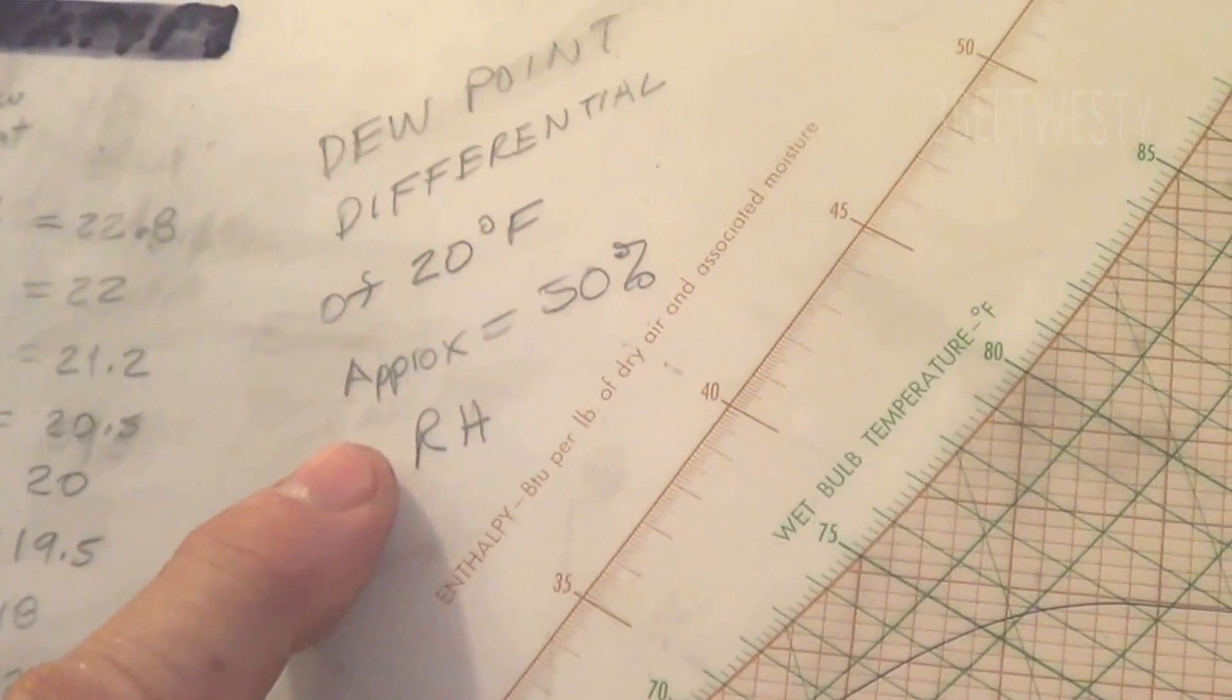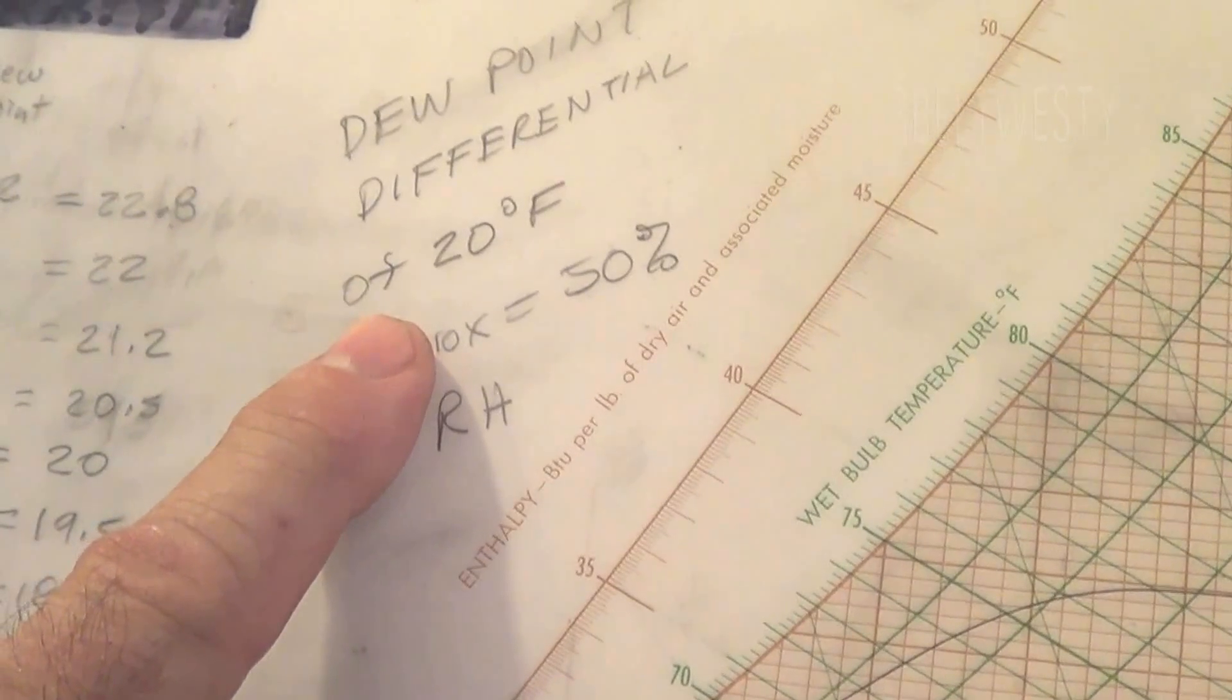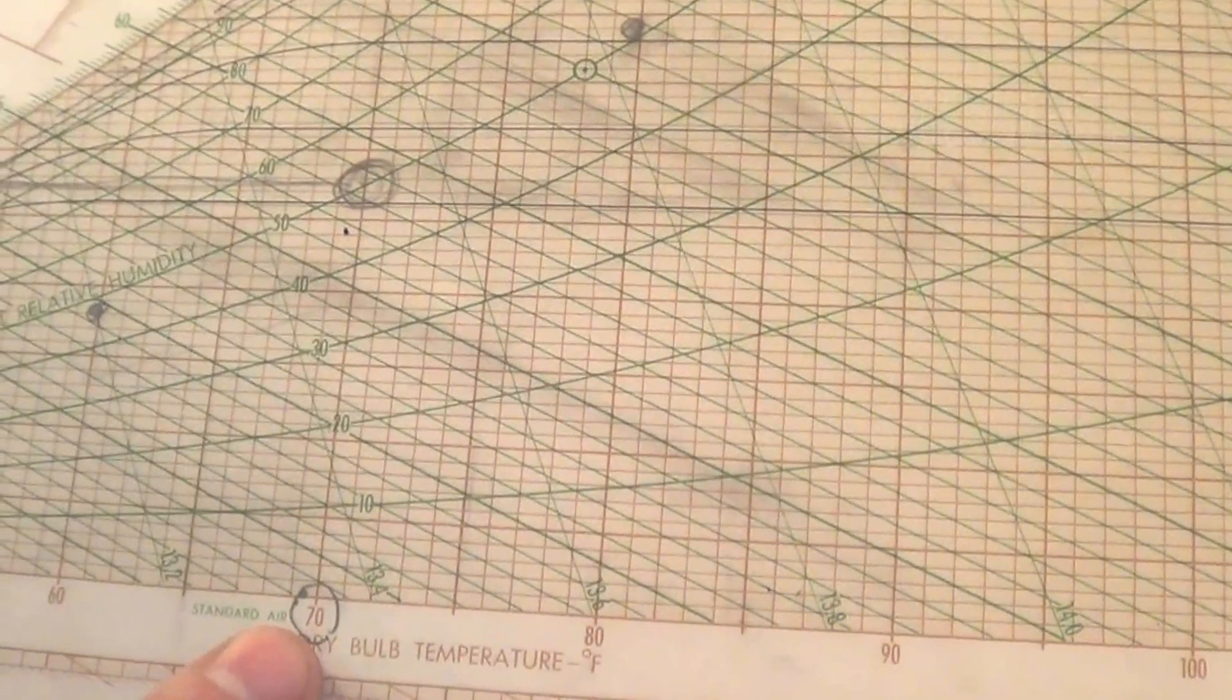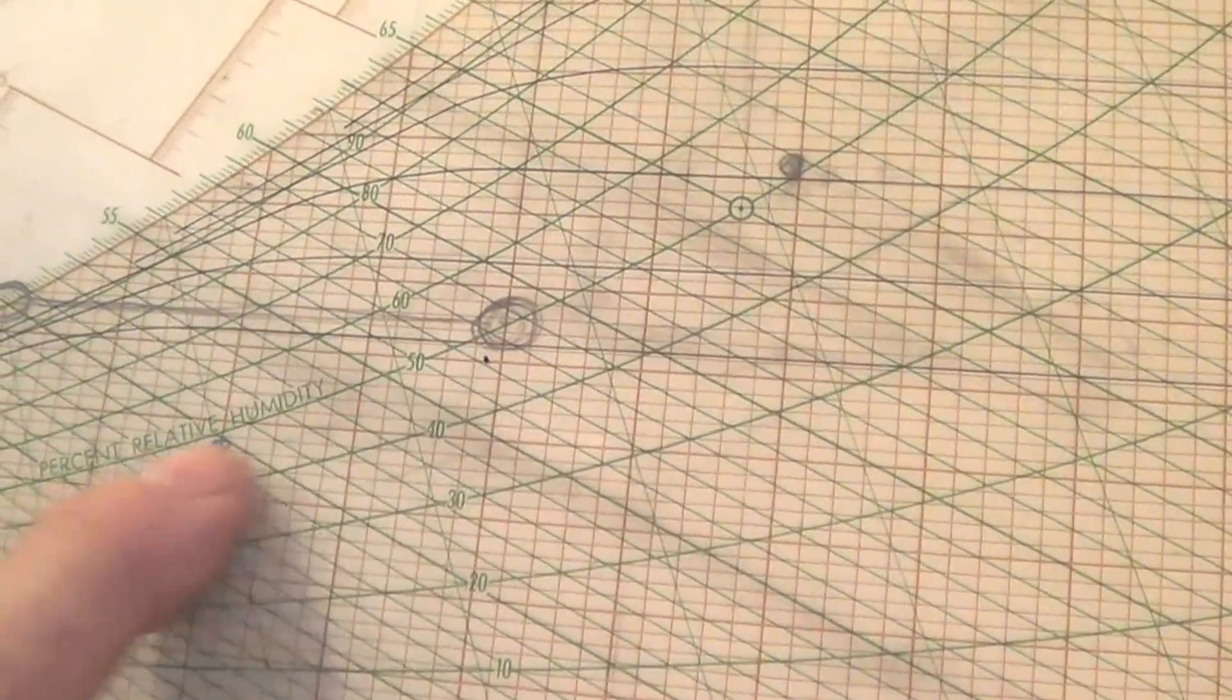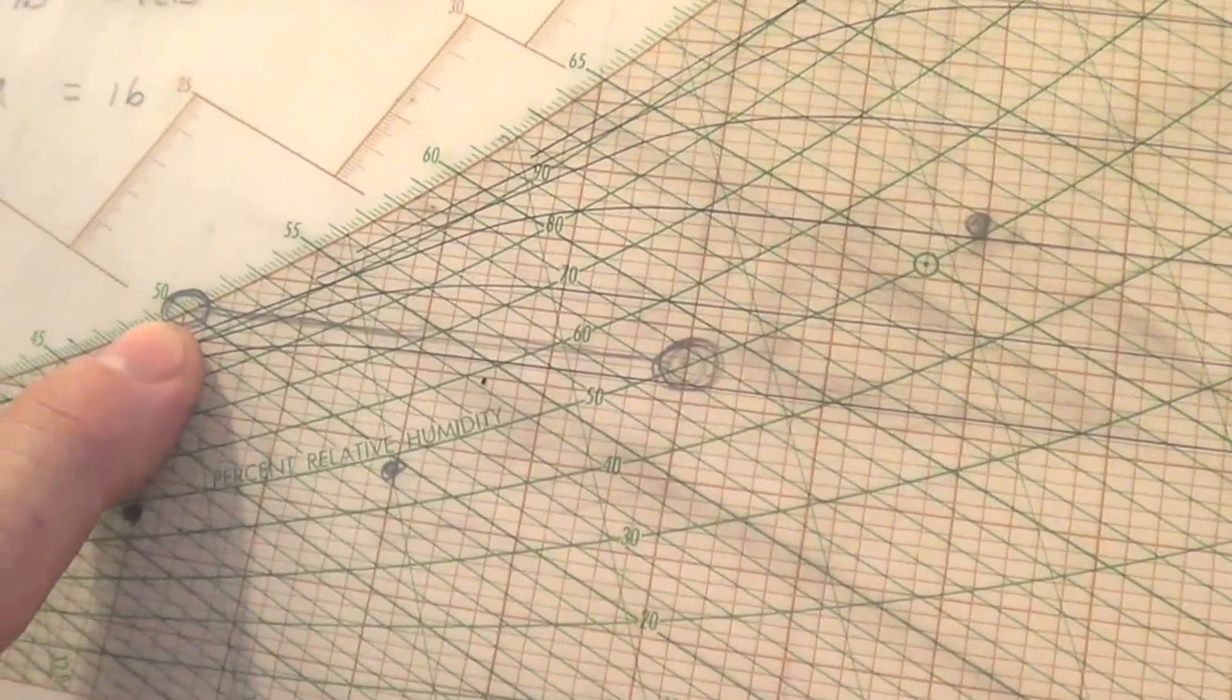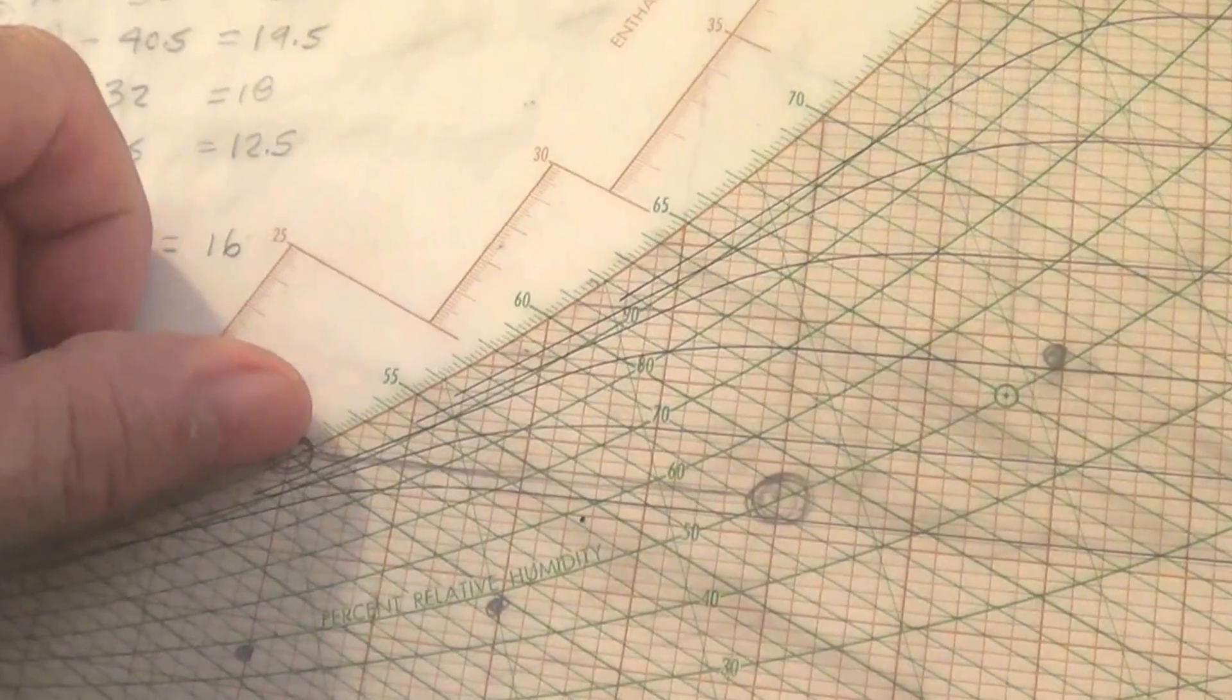Again, this is a dew point differential of 20 degrees between dry bulb and the dew point. If you take, say, 70 degrees here, you go up to the 50% relative humidity line and then you cool this air off. The dew point is 50 degrees here. It's also the wet bulb temperature at saturation.